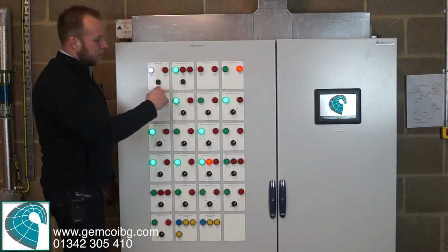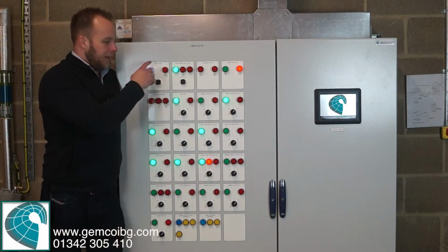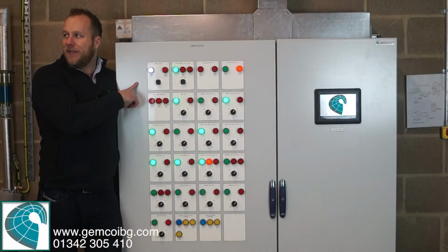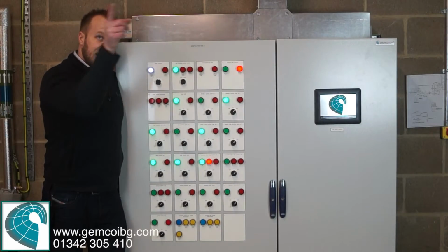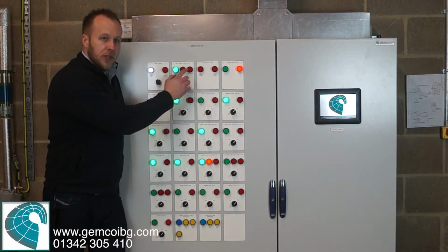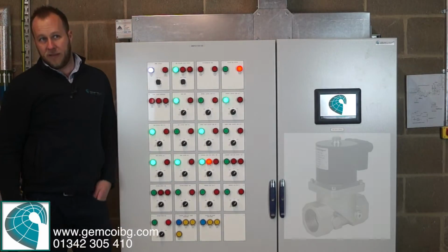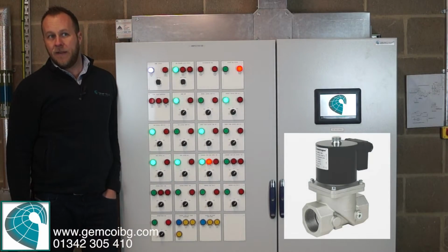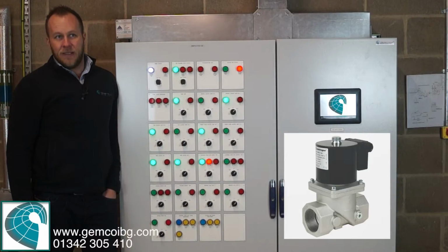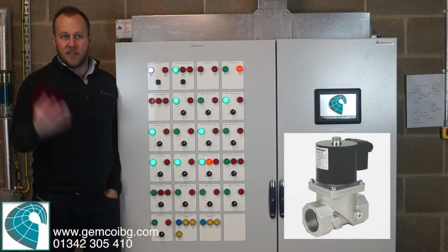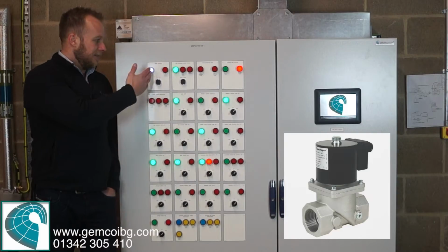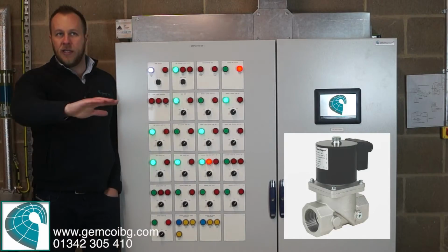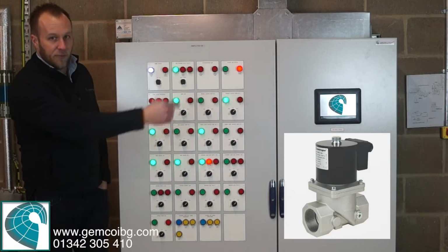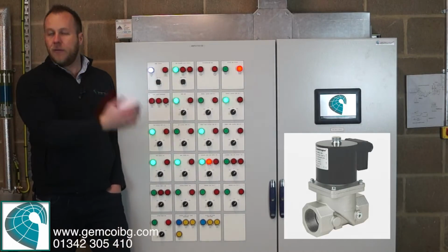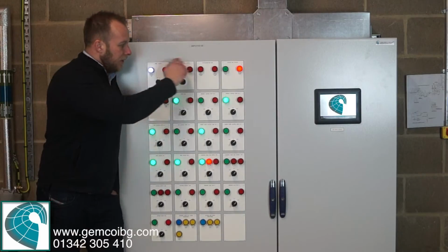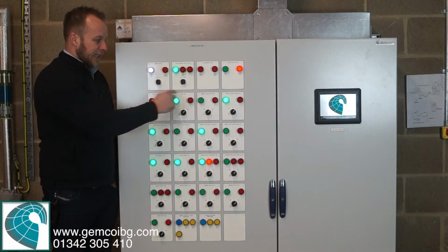Okay? And rupture of any of those, fire alarm, power failure, which you've found out, or that safety circuit that I just mentioned, that will close your gas solenoid valve. Your gas solenoid valve is that big valve on the gas pipe there, with a cable going into it. That's it. Now the purpose of that is if there's a fire or there's overheat or there's a fire alarm, then you want to shut the gas off immediately. Or if there's a fire in the plant room, someone hits the knock-off button, you're going to shut the gas off. So these are the main hardwired safety interlocks into all of this.